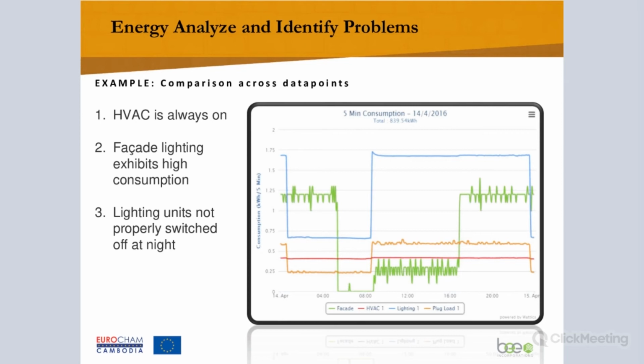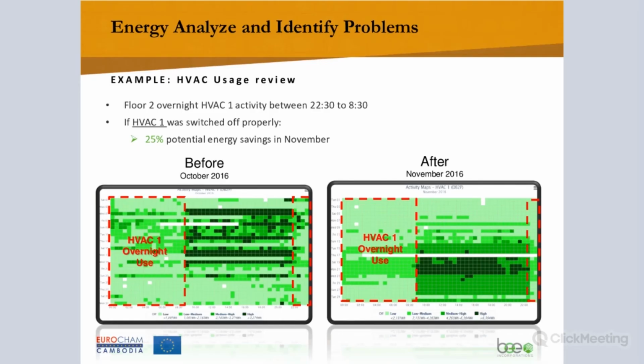Similarly, with the HVAC system, you see it's running 24 hours. That might be necessary if the building operates around the clock, like a hospital. But I believe this was an office building, and they identified issues with the HVAC system not shutting down properly. Doing this kind of daily analysis lets you see where the operational issues are and how you could adjust operations to reduce electricity use.